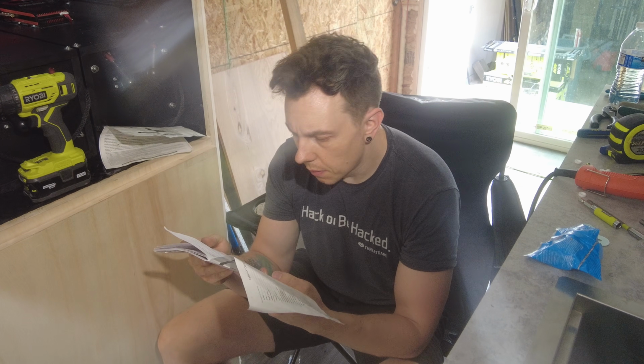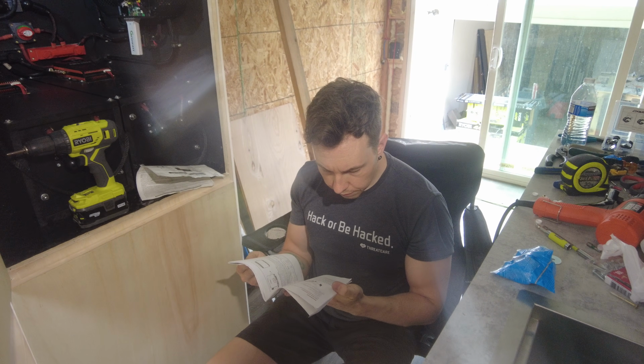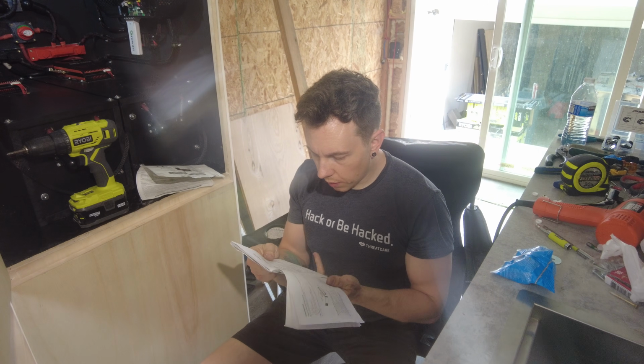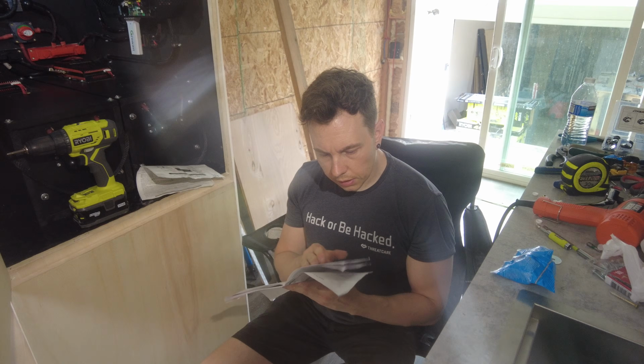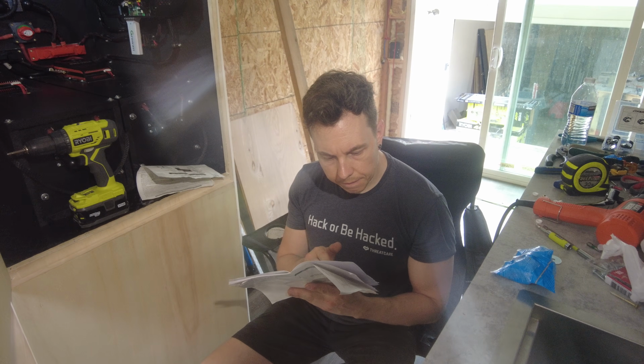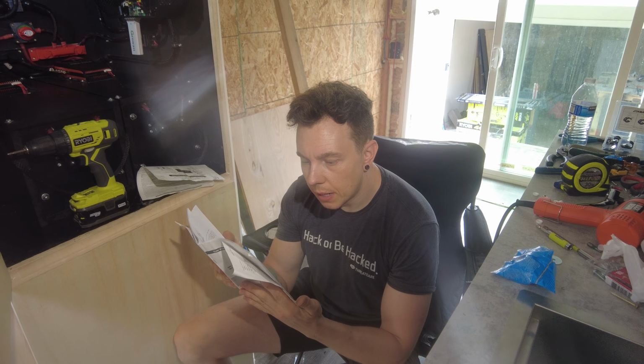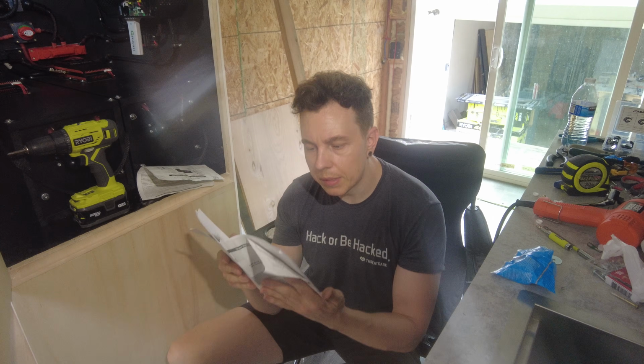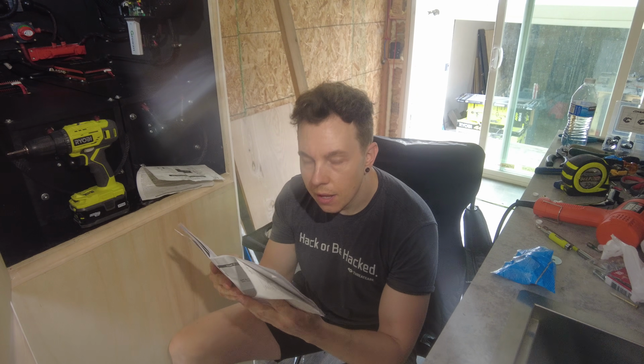Oh, okay, that's good to know. Do not mount the inverter on flammable construction materials. Check. All wiring must be performed by a qualified person. Check. Connecting the batteries with 2-gauge cable. Check. Use appropriate cable size for AC input and output connection. To reduce risk of injury, use the recommended cable size as below: 8-gauge recommended. Check. Before connecting PV modules, install a separate DC circuit breaker between the inverter and PV modules.